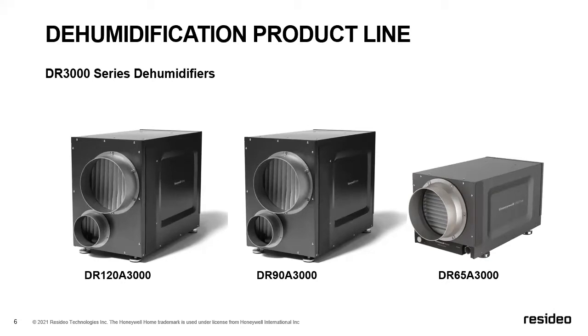Of course, as you can see on the screen, the 65 is missing that secondary intake on the bottom left, which is a ventilation port that we provide on those larger 2 product lines to handle ventilation, intake air, outside air, makeup air, whatever you want to call it. We can handle that ventilation piece with the dehumidifier. So again, DR65, smaller, 65 pints a day. DR90, 90 pint. DR120 would be our 120 pint machine.